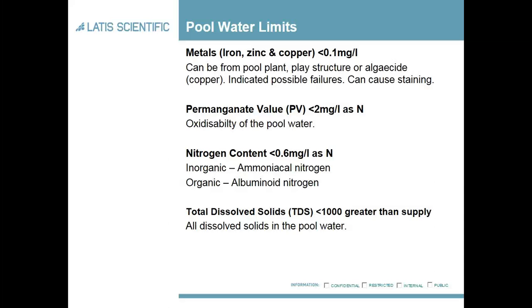Just because you backwash at the times you're supposed to doesn't mean that the TDS will always stay the same. If you think about the number of people using the pool, or the actual nature of what people do in the pool, this affects the loading on the pool. It will have to be monitored as you go along, and you can adjust backwashing to work longer or more frequently.